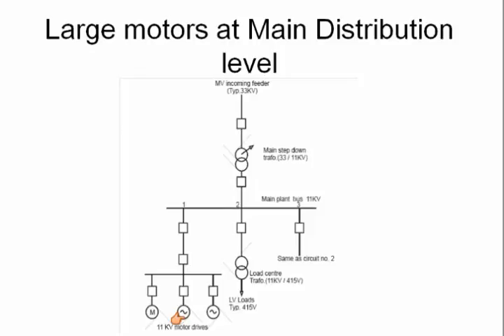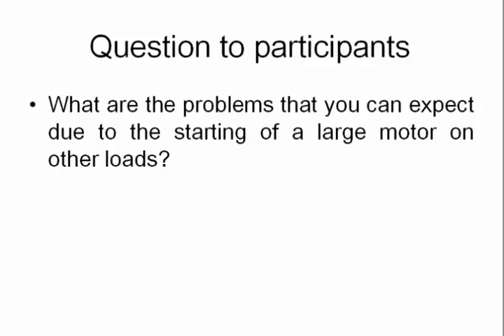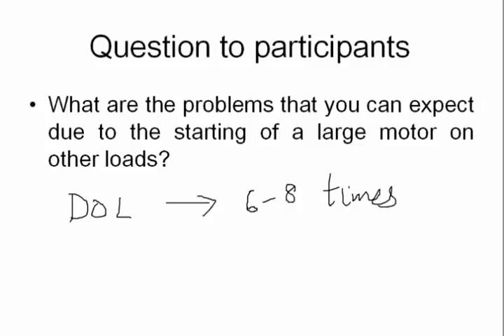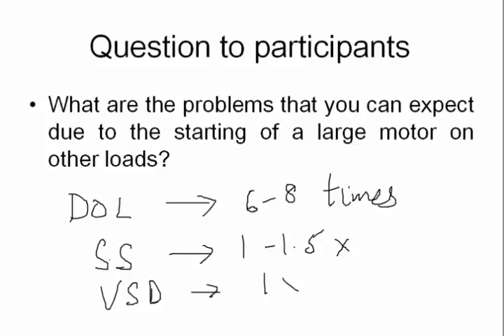So what are the problems that you can expect due to starting of a large motor on other loads? Well, when a large motor starts, if it is on DOL, direct online starter, what's the typical starting current? In terms of normal range, typically what's the range of starting current? Because of that, there is a large voltage drop which can cause voltage dip, flicker, issues with other loads and other motors. With a soft starter, it might be 1 to 1.5 times. With a VFD, you can regulate it to almost 1 time. But these are all expensive options used for bigger motors.